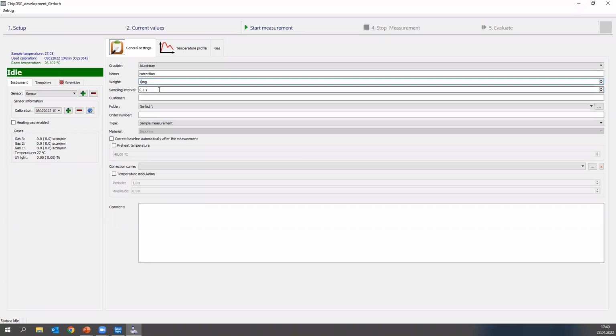Then a sampling interval of 0.1 second is quite okay. We have no customer, this is my folder, and there's no order number. But what we have to change is that we want to do a correction measurement. Now we can already see that we are not allowed to choose any correction curve anymore, and this is important. If you want to measure with temperature modulation and chip DSC, don't use any correction curve. The software does this by itself, so there's no need for any correction curve here.